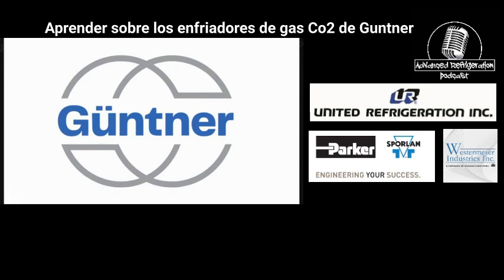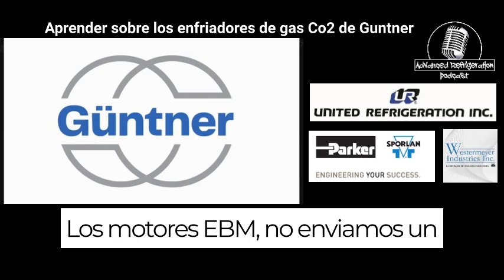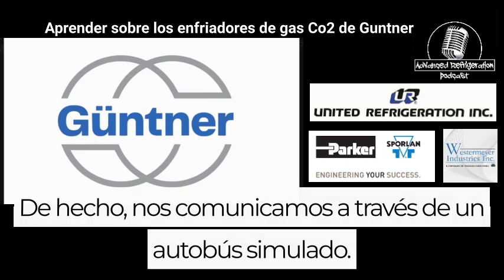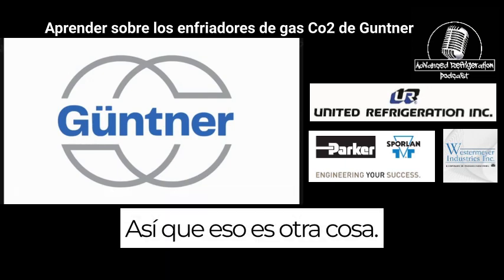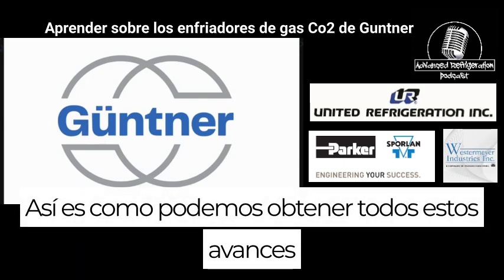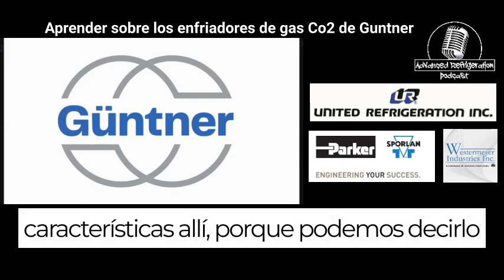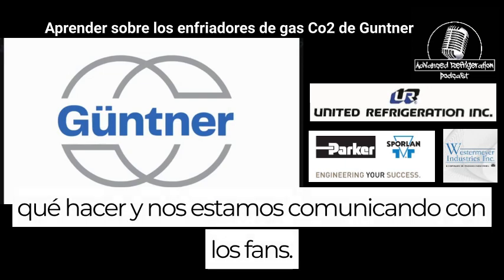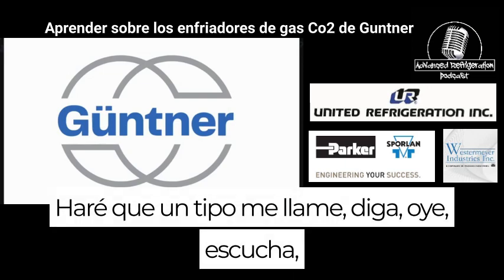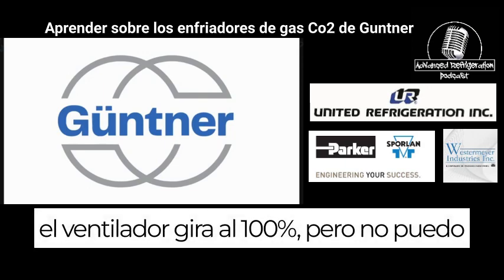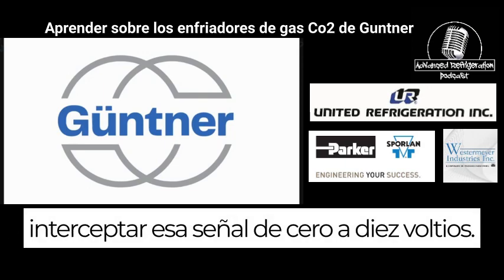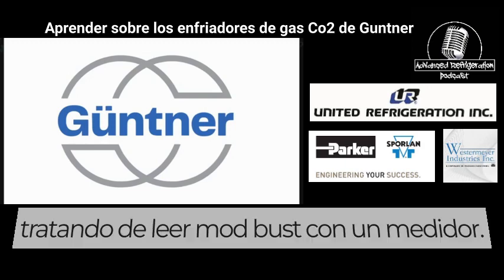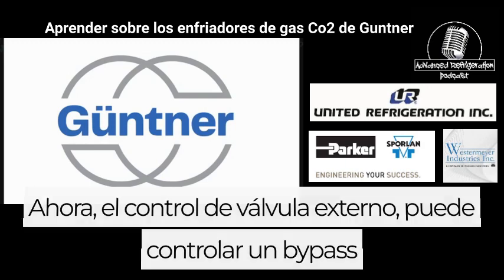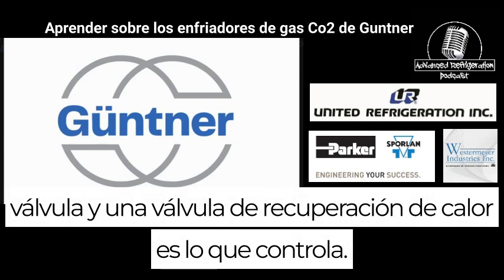Well, we're not. So with the EBM motors, we don't send a 0 to 10 volt signal to them. We actually communicate via Modbus. That's how we can get all these advanced features in there, because we're able to tell it what to do, and we're communicating with the fans. I'll get some guy calling me, saying, hey, listen, the fan's spinning at 100%, but I can't intercept that 0 to 10 volt signal. I don't know what it's doing, because they're trying to read Modbus with a meter. Now, the external valve control, you can control a bypass valve and a heat recovery valve.